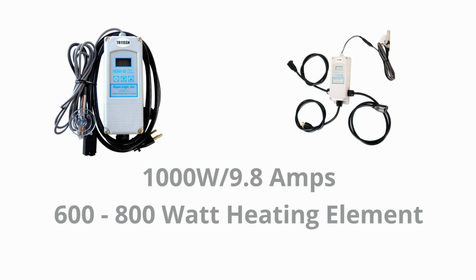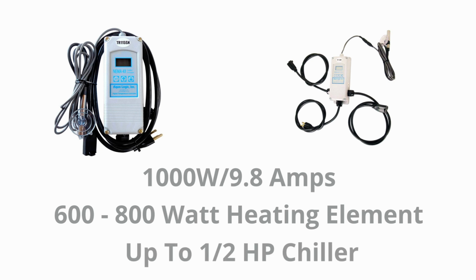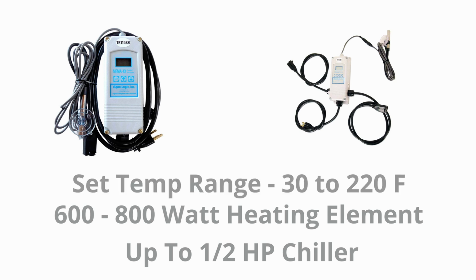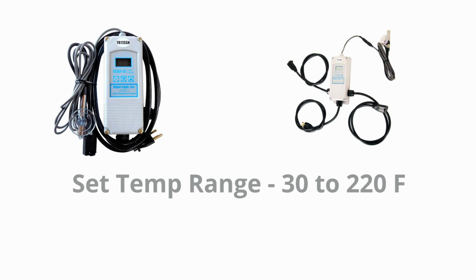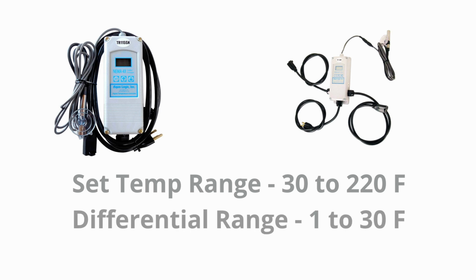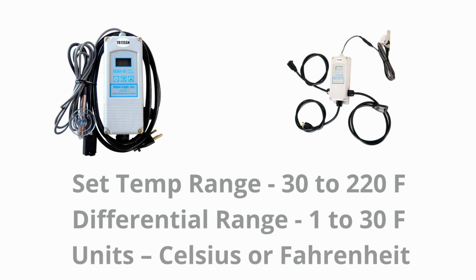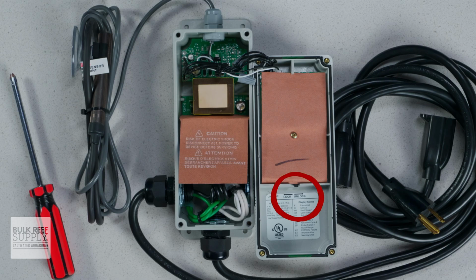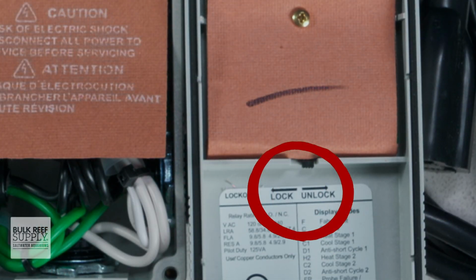For cooling, that works out to roughly a half horsepower chiller, but it's always best to play it safe and double check the amperage of the chiller that you want to run rather than just relying on the horsepower. They offer a wide set temperature range of 30 to 220 degrees Fahrenheit with a differential of as little as 1 degree up to 30 degrees Fahrenheit. You can choose between Celsius and Fahrenheit if you prefer one over the other, plus it allows you to lock the keypad so curious or fumbly fingers don't accidentally change the settings.